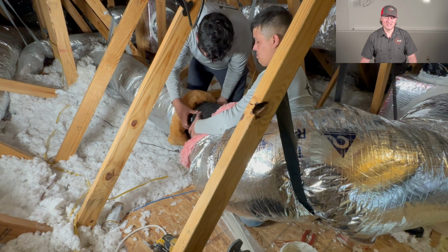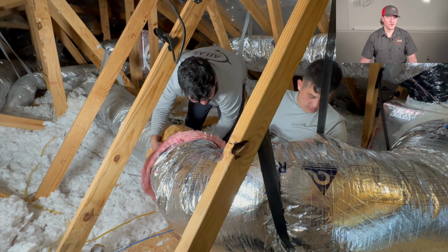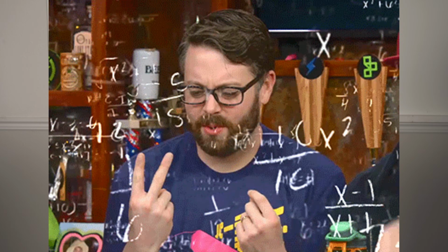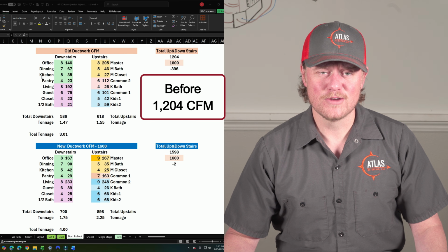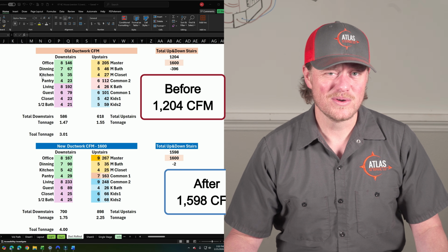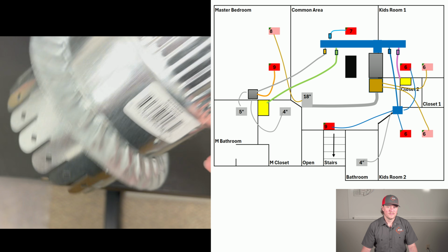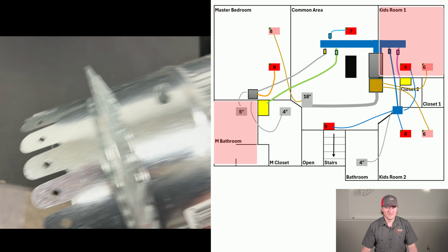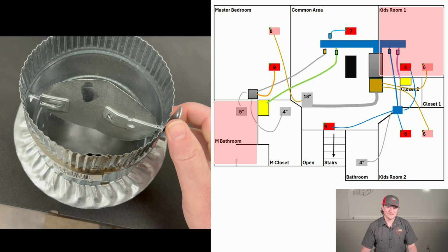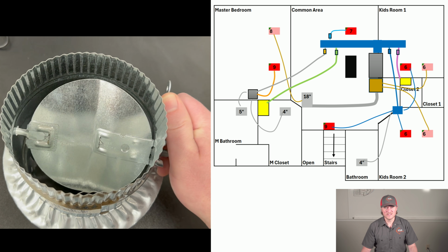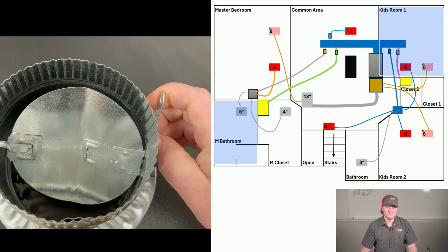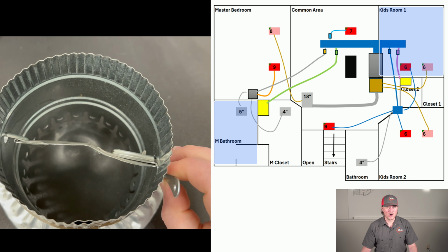We were very limited with our options when it came to upsizing our ductwork. A tight attic, not able to get to the downstairs ductwork, which is very common for a lot of folks that have two-story homes. However, with all these challenges, we were still able to come up with a duct design using just simple math. We're needing to add an additional ton of airflow for the overall ductwork, and we were able to do just that. That being said, did we solve everything? No, but it got us 80 to 90% there. All that's left is some airflow balancing to redirect the air where it needs to go. And that should finally take care of all of our hot and cold spots.